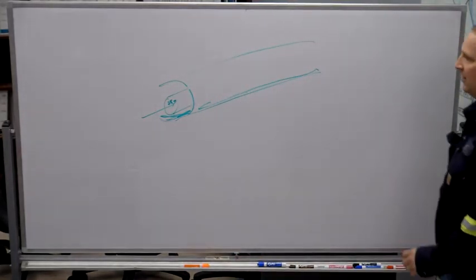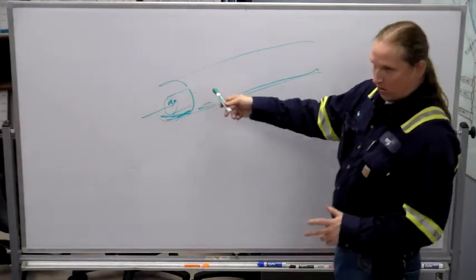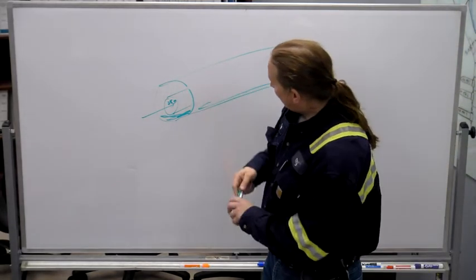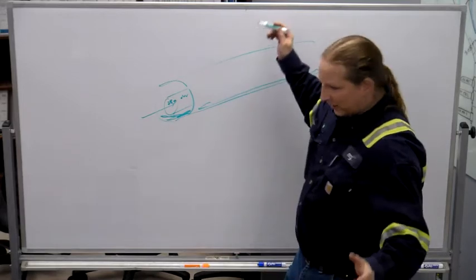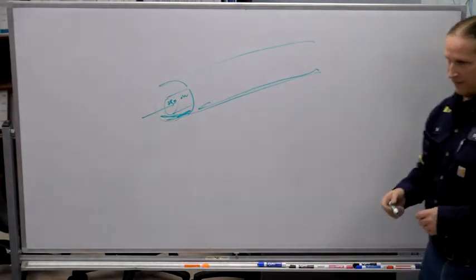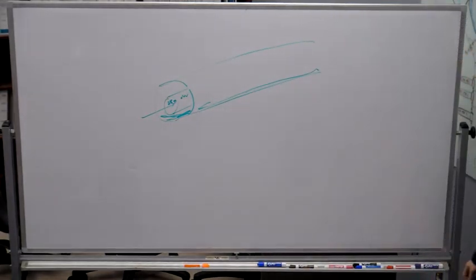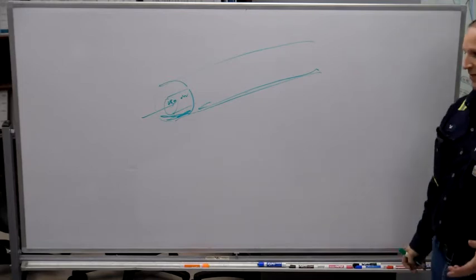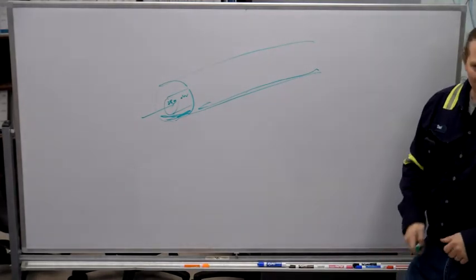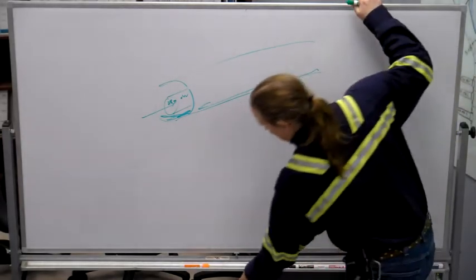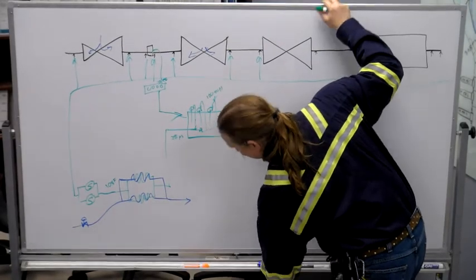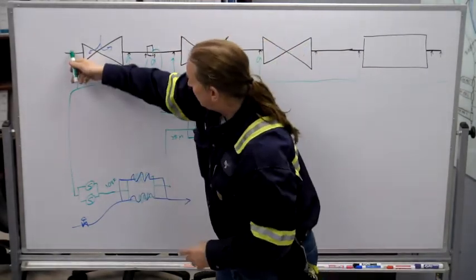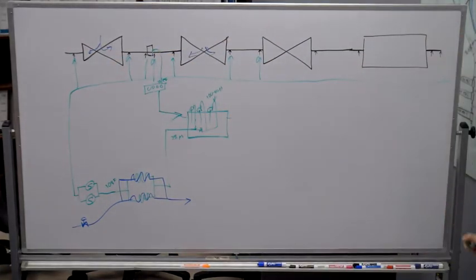The reason for this is that in a crack, rupture, oil leak kind of situation, a fine mist oil spray is like a very dangerous environment to have. So they designed it so that if you get that crack, instead of leaking in the air, it leaks and gets captured by the outside pipe and just drains back to the tank. Now, this can affect the flow to the bearings, and you can have bearings start running hotter, but you will not have a space that's dangerous to us. It's just the equipment. It's just the multi-million dollar equipment that we're responsible for taking care of. So it comes from the tank and then it ties into this header and then it goes to the bearings and it goes back from the bearings and back to the tank. And that is the lube oil system.